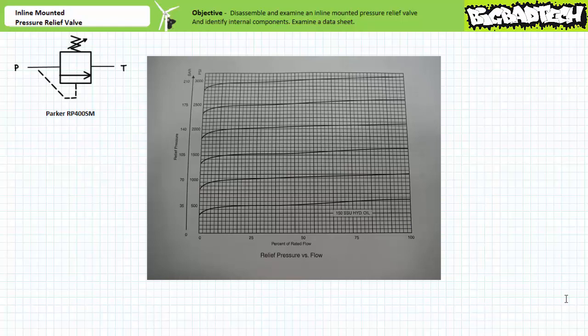Let's use the bottom curve to approximate how this valve would function. This curve suggests that the pressure relief valve would accommodate full flow or 6 gallons per minute at roughly 593 PSI. Given this exact adjustment setting described by the curve and a pump capable of producing, let's say, 3 gallons per minute, we could expect the relief valve to fully open at roughly 500 PSI. At the far left regions of this curve, this suggests that the valve just begins cracking open at approximately 314.1 PSI. Anything below this pressure, the pressure relief valve remains completely closed. Above this pressure, the pressure relief valve begins diverting flow to the tank.